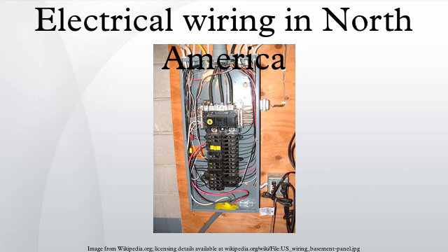For residential wiring, some basic rules given in the NEC: phase wire in a circuit may be black, red, orange insulated wire, sometimes other colors, but never green, gray, or white. Specific exceptions apply, such as a cable running to a switch and back where the white wire will be the hot wire feeding that switch. Another is for a cable used to feed an outlet for 250 VAC 15 or 20 amp appliances that do not need a neutral, there the white is hot. The neutral wire is identified by gray or white insulated wire, perhaps using stripes or markings.